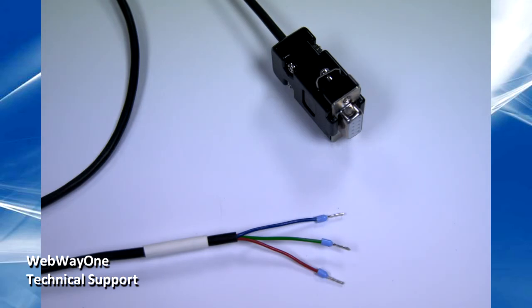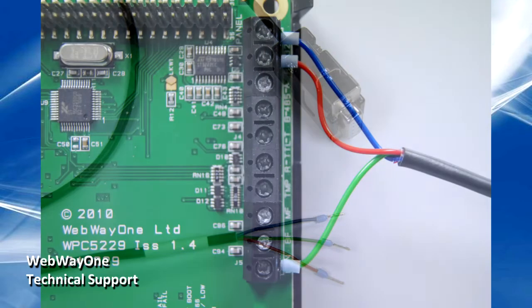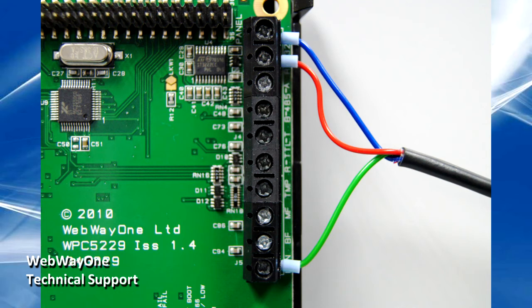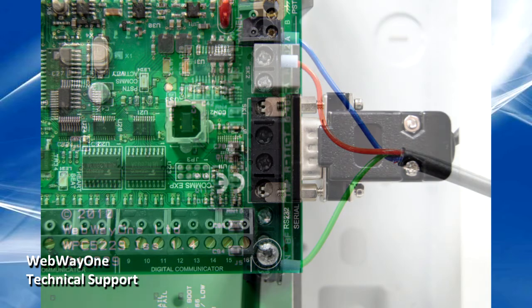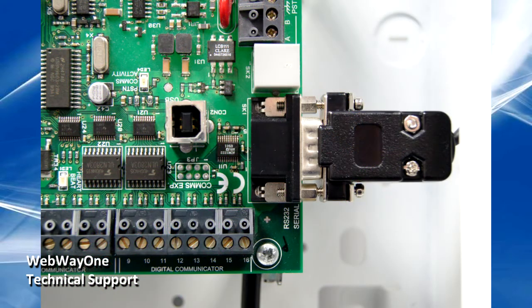Let's look at the physical wiring. The S-series mainboard assembly has a 9-way D-type connector at the top right. Webway can provide a special cable with the relevant connector to allow serial connectivity. On the Webway board, connect the green wire to the return terminal, the red wire to the 232 interface R terminal, and the blue wire to the 232 interface T terminal. Finally, connect the D-type to the 232 connector on the Scantronic.